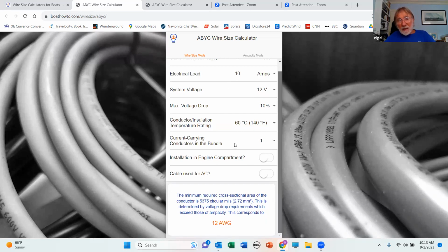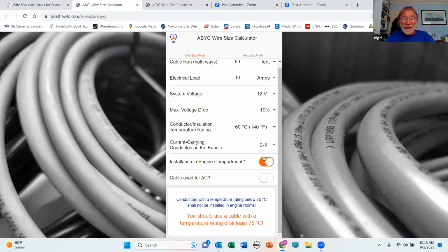Now we've got the bundling factor. So let's say we're in a bundle here with two or three other conductors. So we may have to derate for that. And now we've got the ambient temperature issue. Is this going through an engine compartment? An engine compartment is basically a generic term for any hot area of the boat. And if any section of the conductor is going through a hot area, we're going to click that. And we're not in an AC circuit. And then down the bottom, it tells us the minimum size conductor we should use.